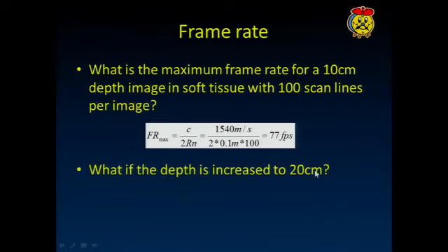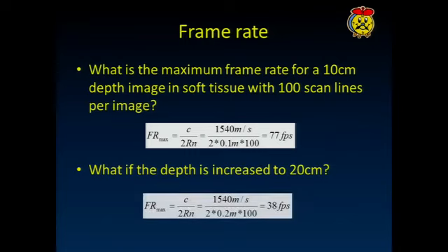What if our depth increases to 20 centimeters? Well, now it's going to take twice as long for us to sit and wait for echoes as sound propagates the additional 10 centimeters in and the additional 10 centimeters back out. So our maximum frame rate is going to drop in half, not surprising.